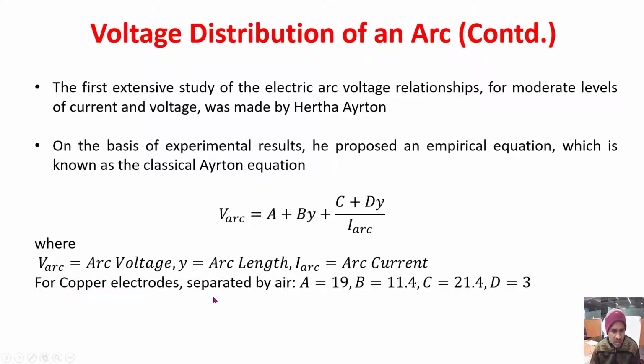For copper electrodes separated by air, A equals 19, B equals 11.4, C equals 21.4, and D equals 3. So this nonlinear equation is typically used for arc voltage estimation with position.